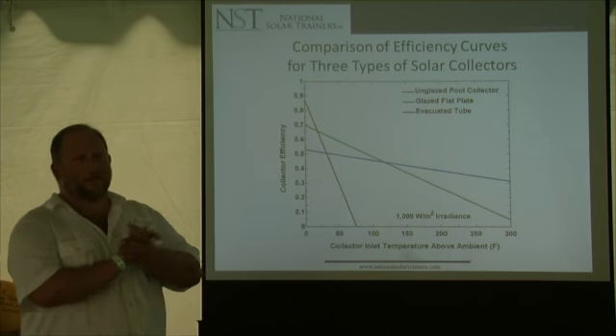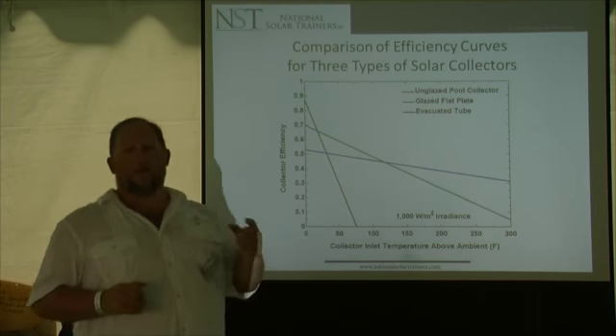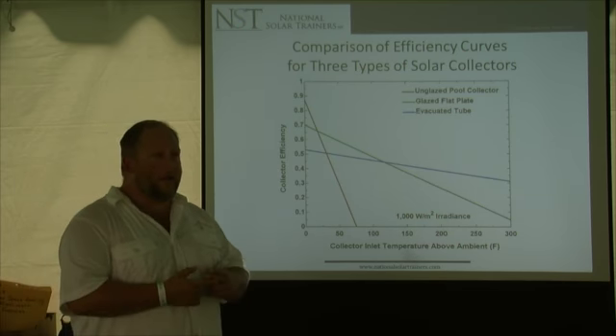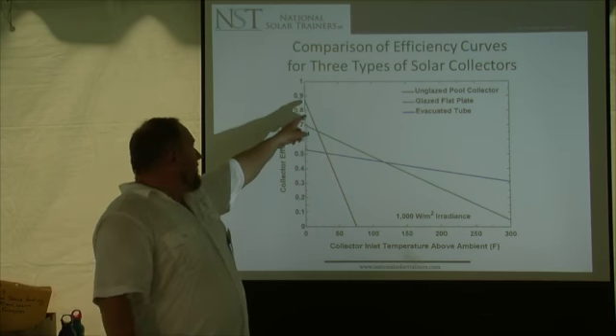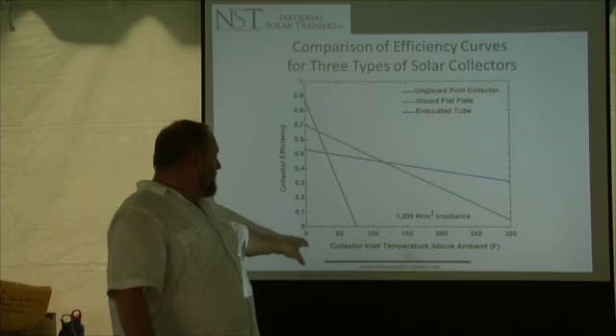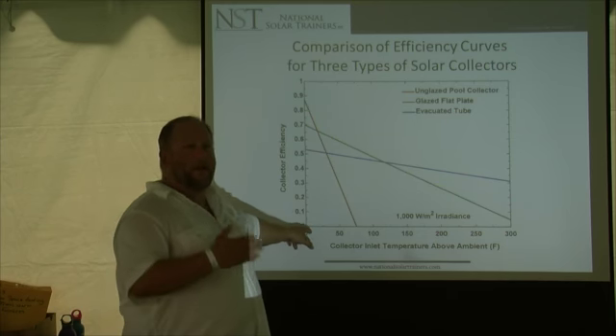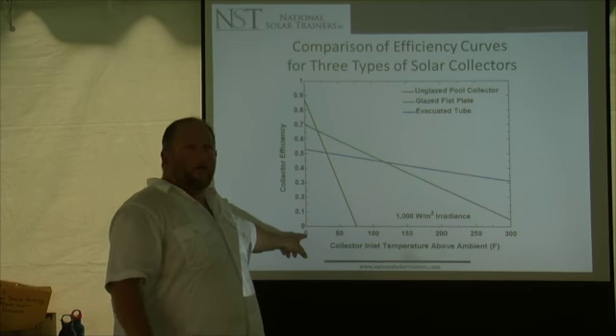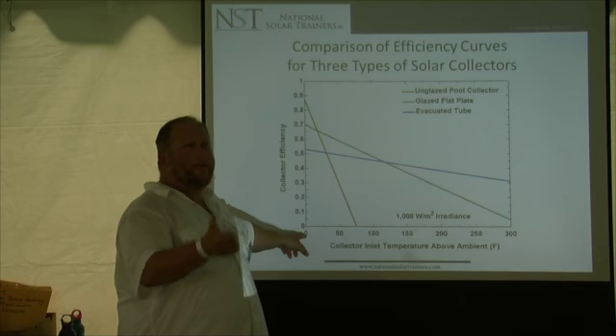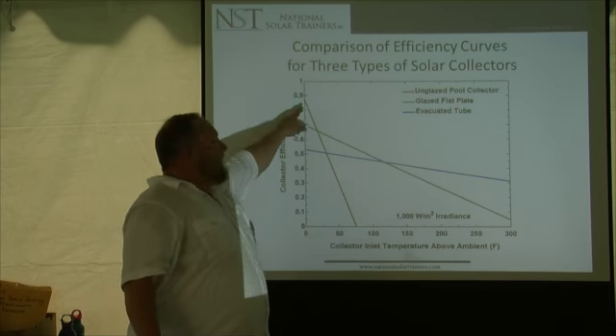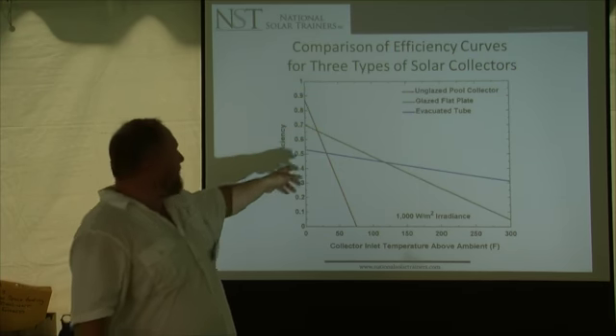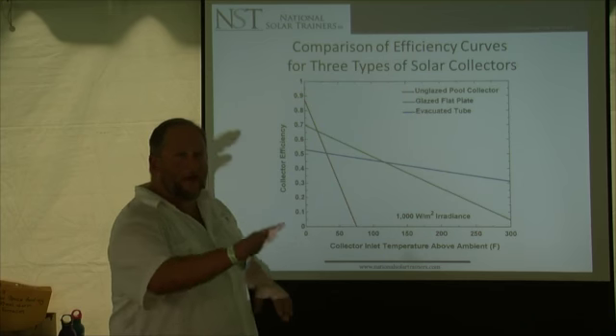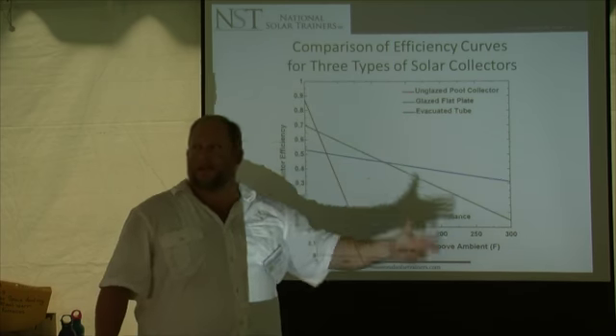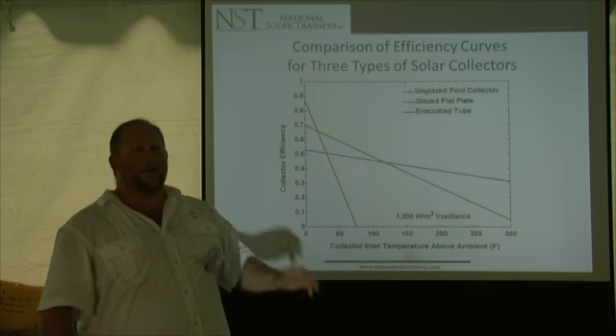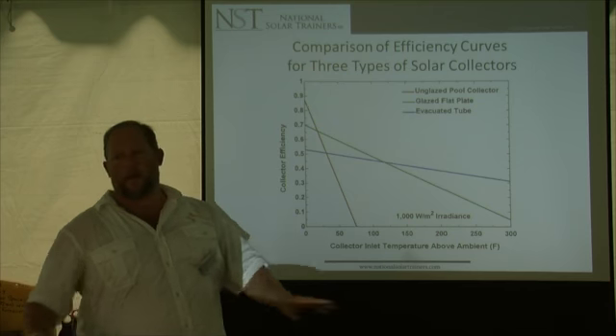This is the efficiency curve of the three types I'm referring to: unglazed collectors, flat plate collectors, and vacuum tubes. The unglazed collectors do better. Down here is the difference between collector temperature and air temperature - zero is where they're equal. Under that condition, the unglazed pool collectors do better. But once the air temperature begins to drop, the efficiency advantage goes to vacuum tubes. Vacuum tubes clearly do much better in cold climates, there's no doubt about it.